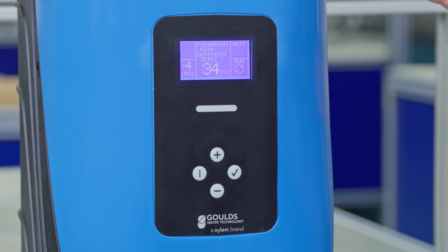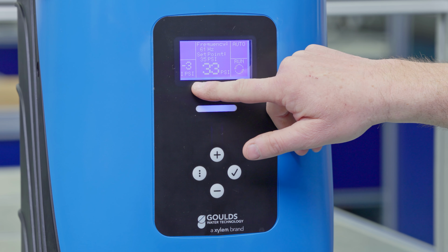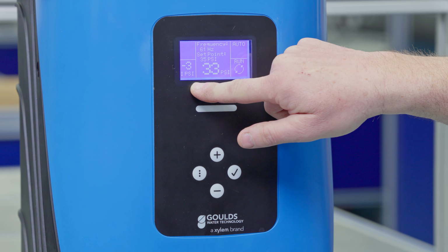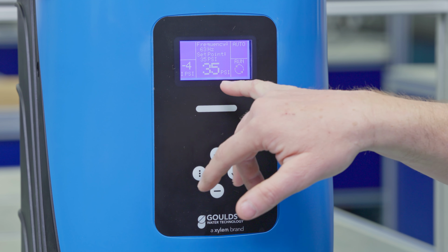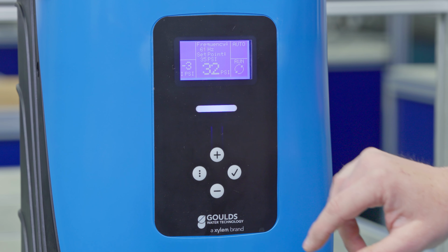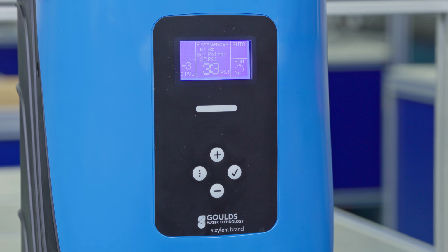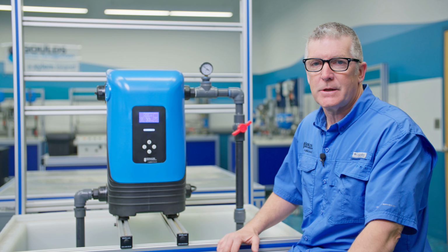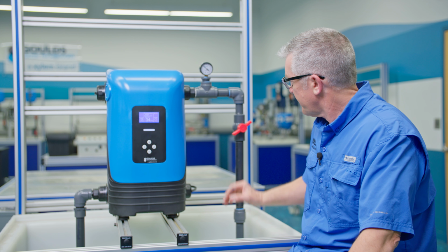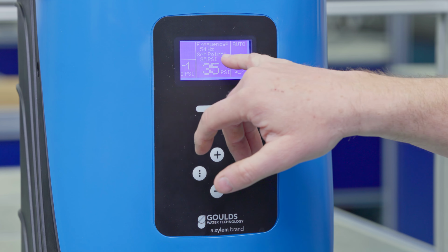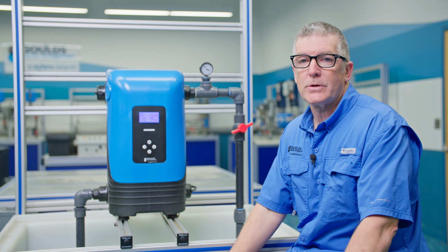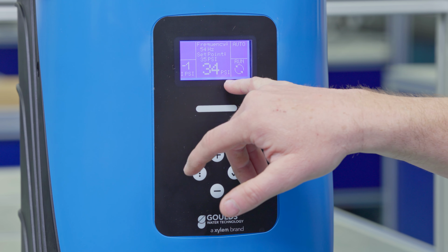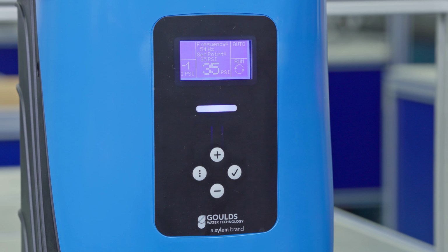So we'll take a quick look at the user interface, the screen at this point. On the bottom left, that is the suction pressure. Now, of course, we are in a lift condition. That's why it is negative currently. We can see frequency, currently somewhere around 60, 61 hertz. Set point is 35. That's where we've set that constant pressure to run at. We are matching that currently, 34, 35 PSI.